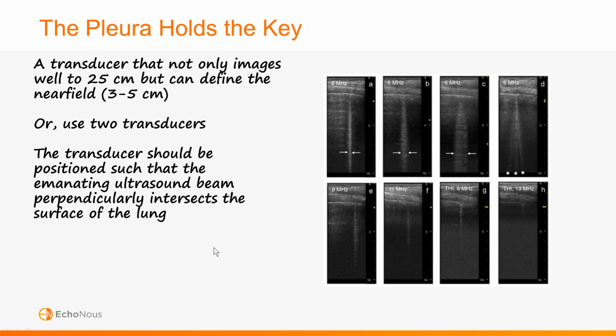Before we do, it's important again to bring us back to Dr. Kamada's study, and this is a great one that he did and published, and looked at all of the effects that different settings can have. So you not only need a transducer that can image maybe to 25 centimeters, especially with some of our heavier patients, but define the near field at 3 to 5 centimeters in depth, or you have to use 2 transducers, but obviously that affects your workflow. And now with the decontamination measures required, that really increases your time.